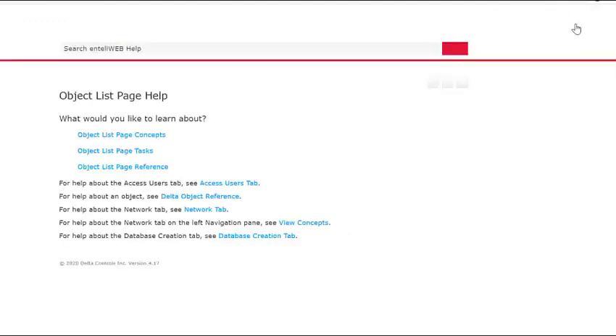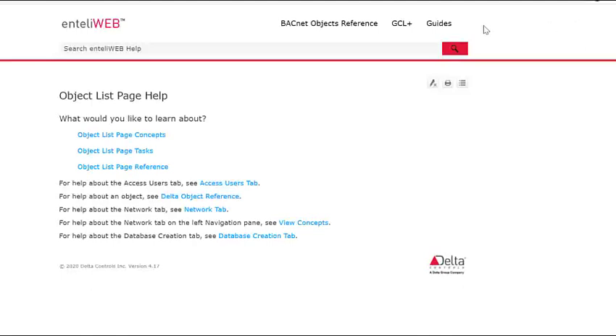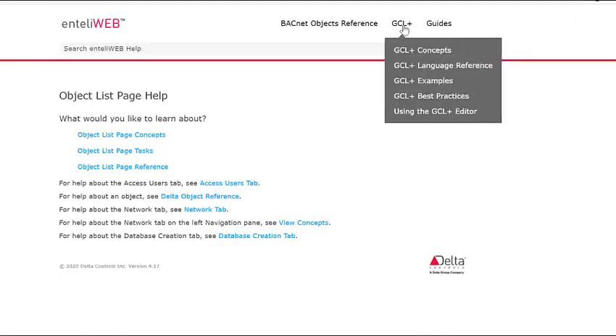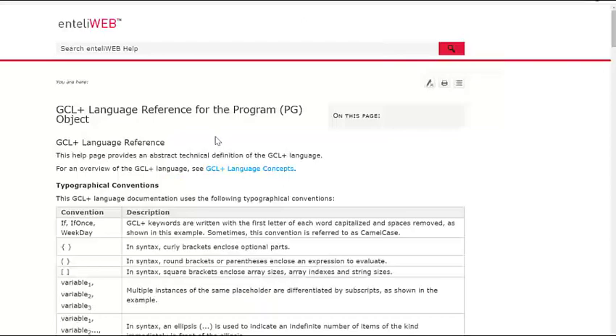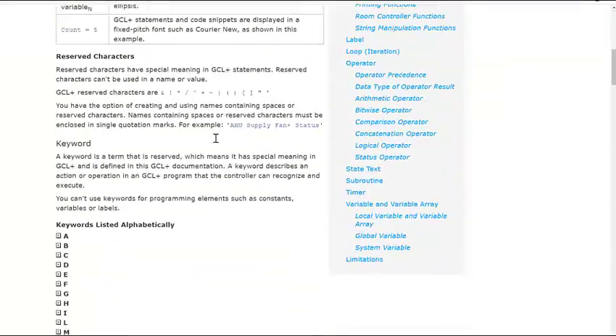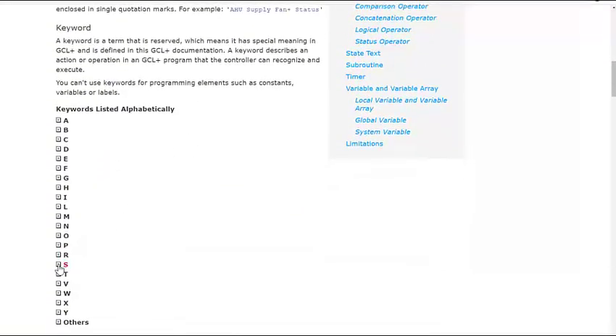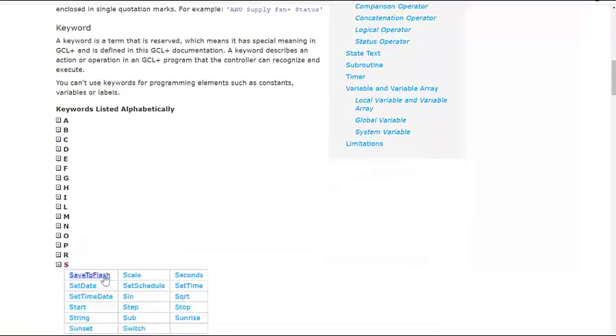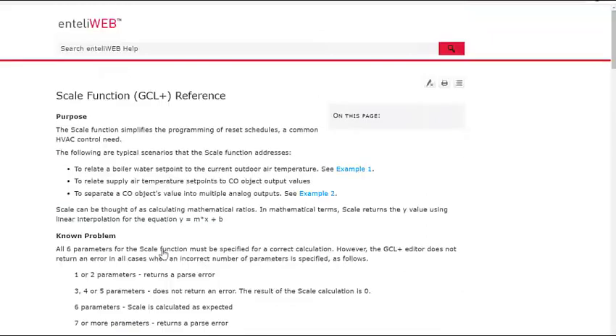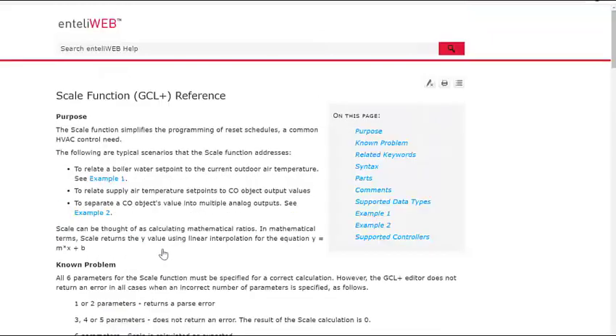There is a function commonly used in GCL Plus called scale. A scale function is a reset. It is used to convert one range of numbers into another range. It is used all the time to calculate heating supply water temperature set point based on changing outdoor air temperature.